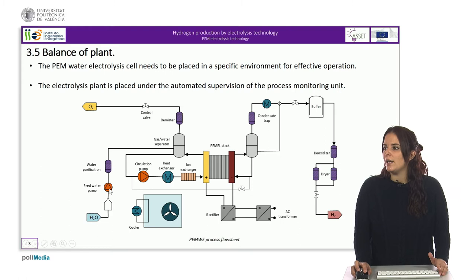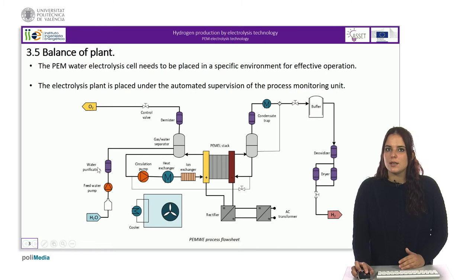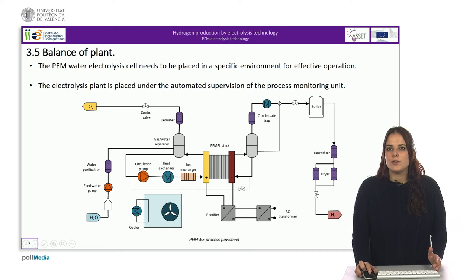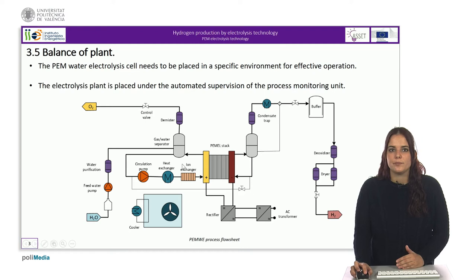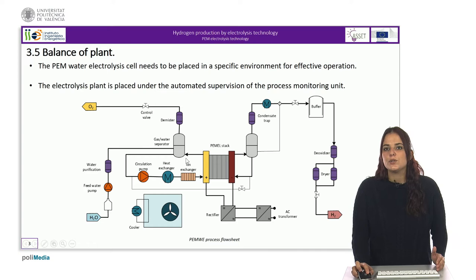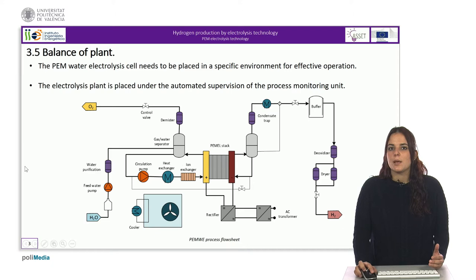Then an AC-DC rectifier produces the appropriate DC power source required by the electrolysis module. On the left, we have the purification system, where purified water is provided by the water management unit that takes tap water and performs several purification steps required by the process. During operation, the water is pumped through the stack by the water circulation unit, where ion exchange resins are used to maintain the required level of water purity. In this loop, we can also find a heat exchanger used to extract the excess heat released by the electrolysis unit.